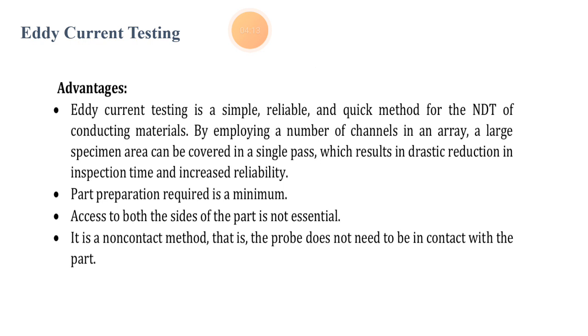There are various advantages of eddy current testing. First, it is a simple NDT method. By employing a number of channels in an array, a large specimen area can be covered in a single pass, resulting in a reduction in inspection time and increased reliability. Part preparation required is minimal, and access to both sides of the part is not necessary. It is also a non-contact method — the probe does not need to be in contact with the part.